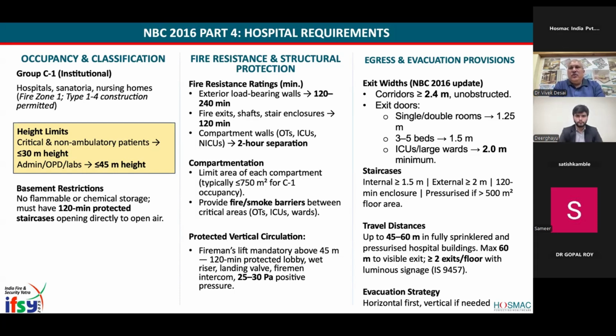Got that. Thank you. Then there are some egress and evacuation provisions. Corridor width should be 2.4 meters clear. It should be a clear height of 2.4 meters. There should be no column coming in between that 2.4 meter, unobstructed. Exit doors, 1.25 meter minimum width for single or double rooms. If it is 3 to 5 bed wards, then 1.5, and larger wards, 2 meters.